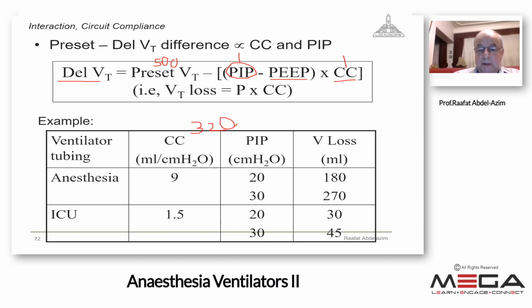The higher the compliance, the more loss. The higher the airway pressure, the more we lose from the preset tidal volume. In ICU ventilators, this effect is less and less because of the low compliance of the breathing circuit that is made from different materials.